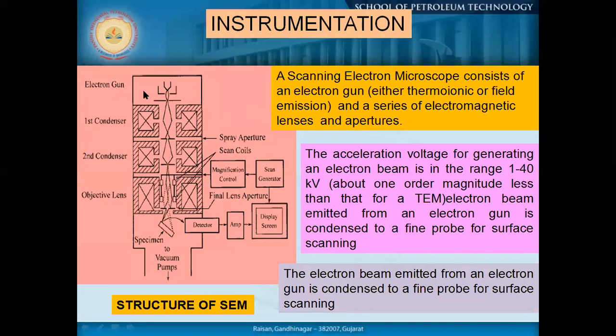Looking at the instrumentation, we use an electron gun, then we have different types of electromagnetic lenses which generally condense the electron beam. We use a high acceleration voltage to generate the electron beam. The electron beam emitted from the electron gun is condensed to a fine probe for surface scanning. With the help of different condenser lenses, we try to converge the electron beam to a very nanometer-scale probe diameter, which helps us obtain the surface features.